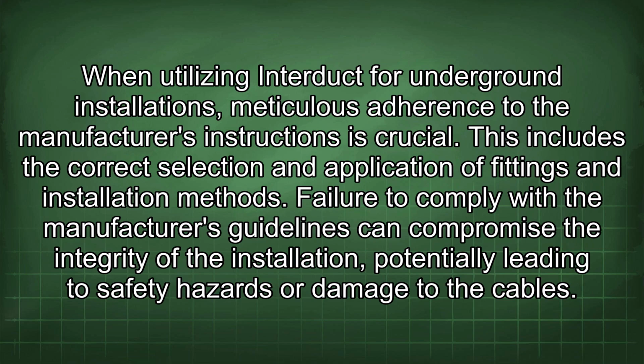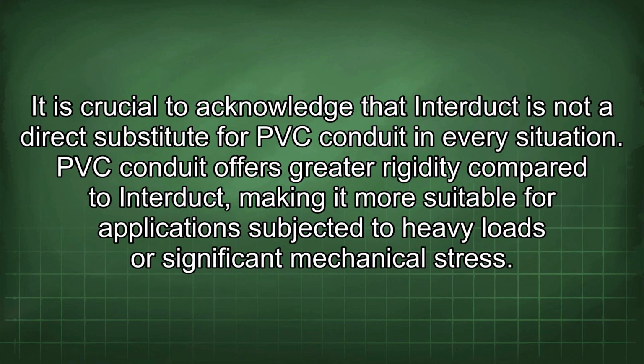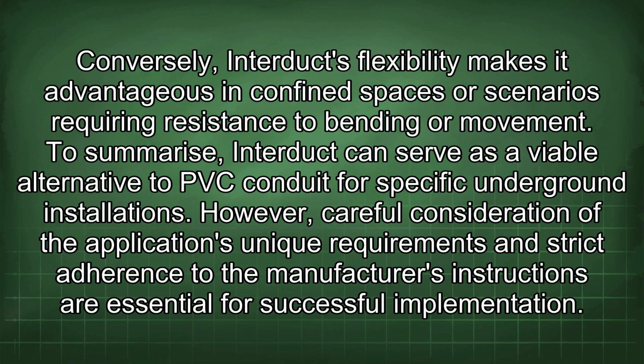damage to the cables. It is crucial to acknowledge that Interduct is not a direct substitute for PVC conduit in every situation. PVC conduit offers greater rigidity compared to Interduct, making it more suitable for applications subjected to heavy loads or significant mechanical stress. Conversely, Interduct's flexibility makes it advantageous in confined spaces or scenarios requiring resistance to bending or movement. To summarize, Interduct can serve as a viable alternative to PVC conduit for specific underground installations. However, careful consideration of the application's unique requirements and strict adherence to the manufacturer's instructions are essential for successful implementation.